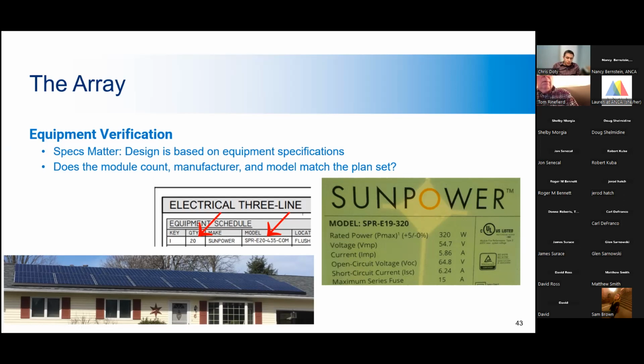Designs are based on precise electrical characteristics of the modules and the string configuration, as well as the inverter output characteristics. So if equipment is substituted in the field, it may become undersized for the new electrical characteristics. A good example of this is the maximum system voltage, which is basically the open circuit voltage. So they are higher for higher wattage panels and even the same wattage modules from different manufacturers. And all of your circuit sizing, overcurrent protection, etc., are designed based on the energy production from the design panels. And you don't want to just assume that the wiring and the system components are all still compatible. If, for instance, the wiring is undersized for what you need, that can cause the wires to melt and can cause a fire hazard.